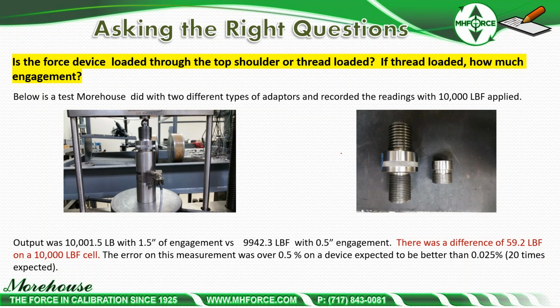And some people can say, well, this is pretty simple. Use a 1.5 engagement. But if the customer sends you nothing, and if you're the person that's sending your equipment out without anything, or you're auditing a customer that's doing this, and you see holes in their load cell, say, where are the adapters that thread into that? Are they being sent with the item for calibration? If not, why not? For all we know, they could be using a 1/2 inch adapter, and that measurement error was 0.5% on a device expected to be better than 0.025, 20 times what was expected.